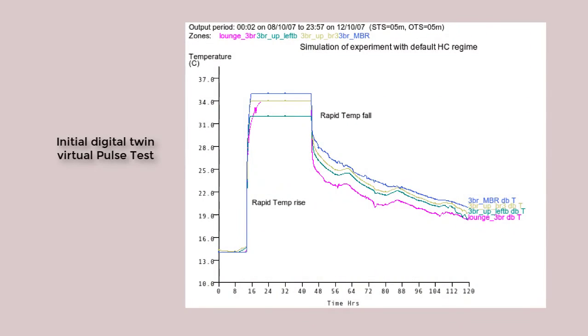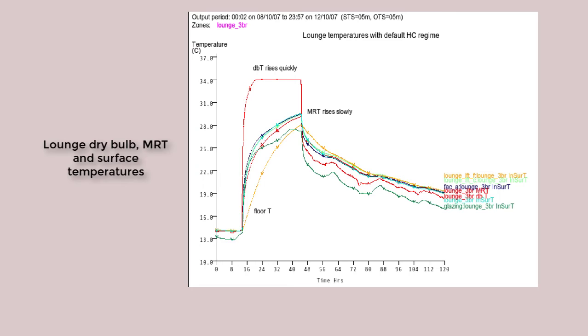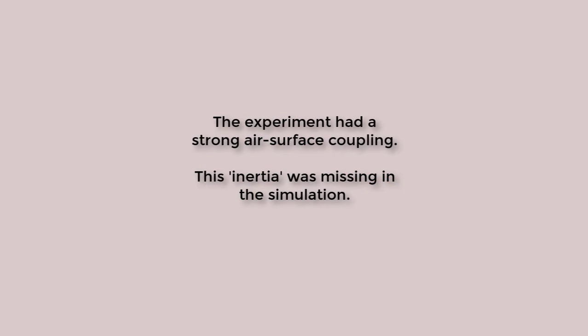When we run the experiment, we get a different story. The air temperature rises very quickly. Looking at the lounge during the warm-up phase of the test, the surface temperatures clearly lag that of the room air temperature, and there is considerable difference between the MRT and the air temperature. It fails to capture the inertia observed in the experiment.